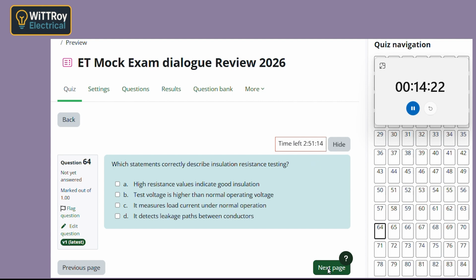Question 64. Which statements correctly describe insulation resistance testing? I said high resistance means good insulation? Yup, that's correct. Think of it like this. If the insulation is healthy, almost no current should leak between conductors. So high resistance means very little leakage.